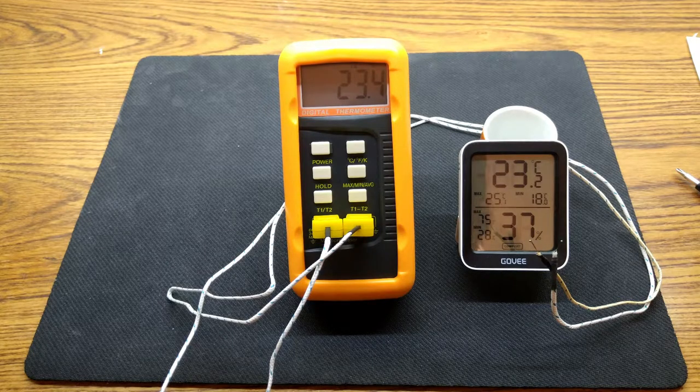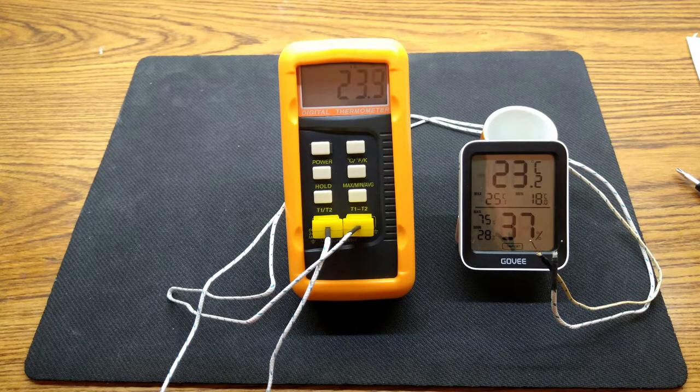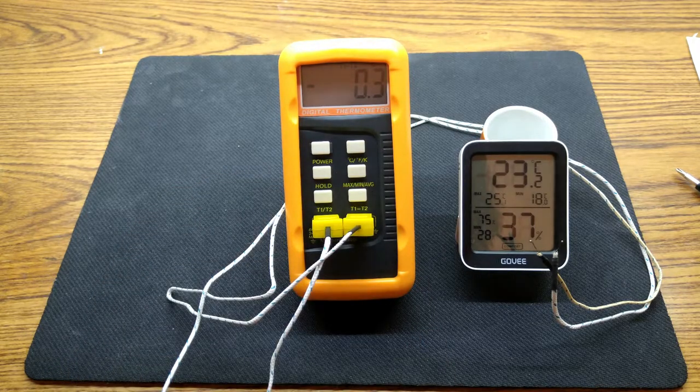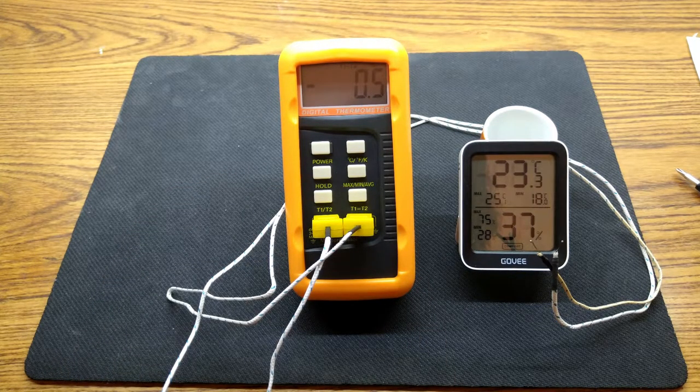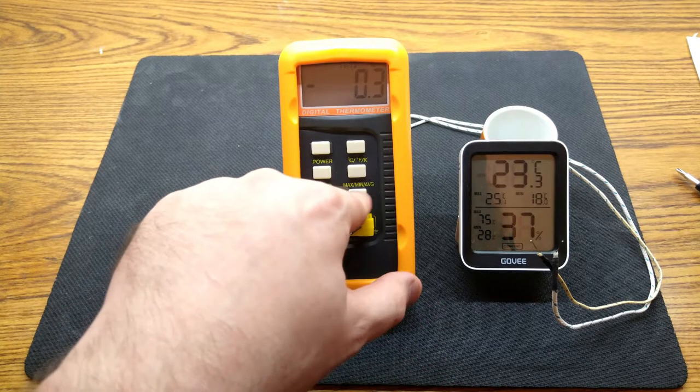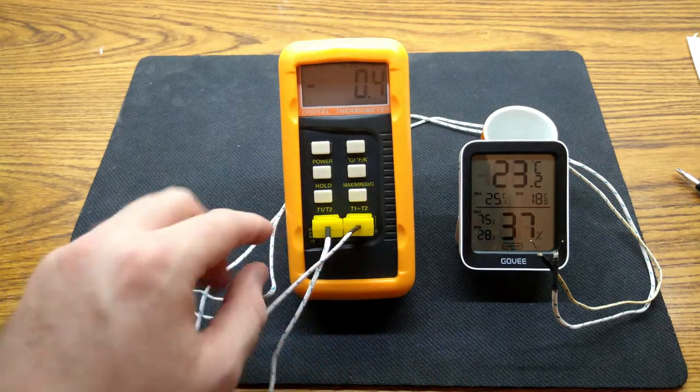So if we have both thermocouples at ambient, we can see the temperature displayed is not the same for both of the probes. There is approximately 0.3 to 0.5 degrees Celsius difference between them. This could be due to either the probes or the internal circuitry, or a combination of both.